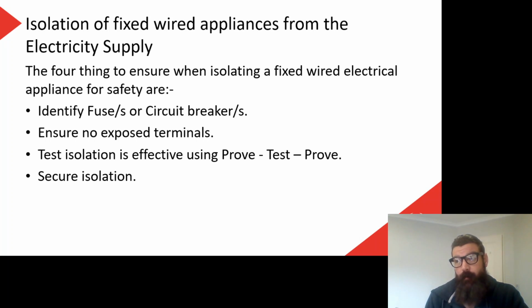I've talked about some of my misadventures in identifying circuit breakers. There's a couple of ways that we could do this. If we can physically trace the cable, that's obviously always going to be the best way because I can physically follow it end to end. If you're working inside a building that is not brand new, as in we're not physically wiring it at that time, you're probably not going to be able to do that.